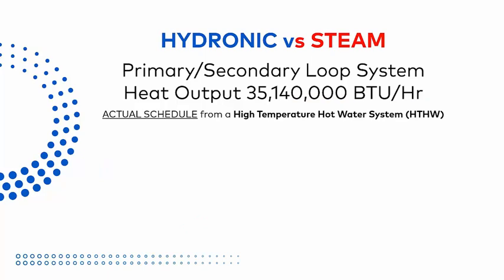On this slide, we see the pumps that are specified for our example project. The pumps used for the campus or building loop are P1 and P2, which are 60 horsepower pumps rated 1150 GPM at 160 feet of head. In this design, one pump runs 100% of the time while the other is the standby. In addition to the loop pumps, we have the individual boiler pumps BP 1, 2, and 3. These are each 15 horsepower pumps rated 700 GPM at 45 feet of head.